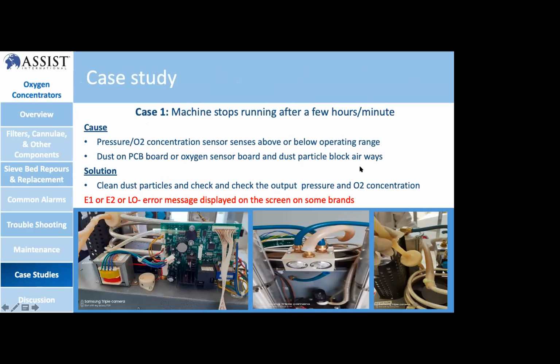When we come to case one, the machine stopped running after a few minutes or hours, as I raised before. The cause we identified for this problem is that the pressure or oxygen concentration sensor senses above or below the operating range. That means the oxygen concentrator has a pressure sensor and an oxygen concentration sensor as components. So when this machine first runs, and after a time it senses the concentration of oxygen delivered to the patient or the pressure of the oxygen gas delivered to the patient, if it is out of range, that means above or below operating ranges, it fails or stops by itself. This is one cause.